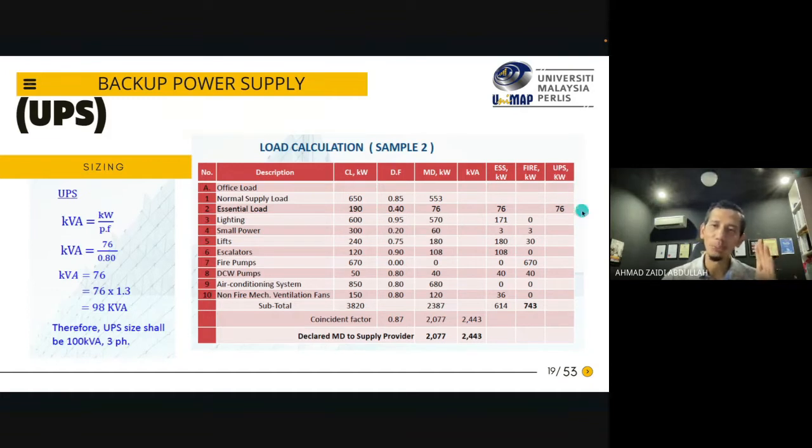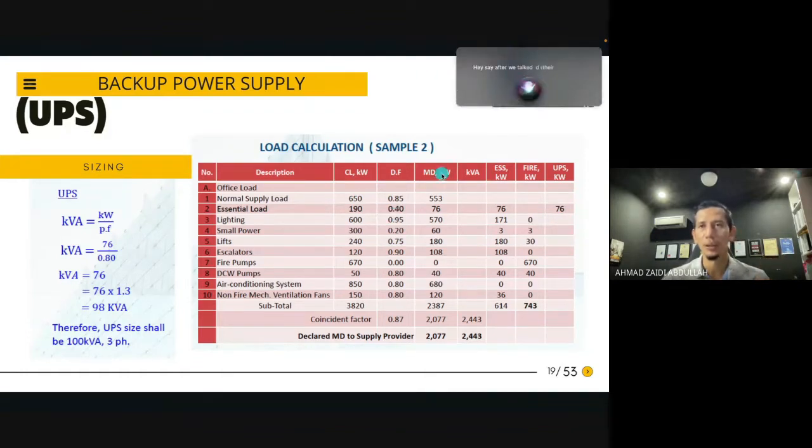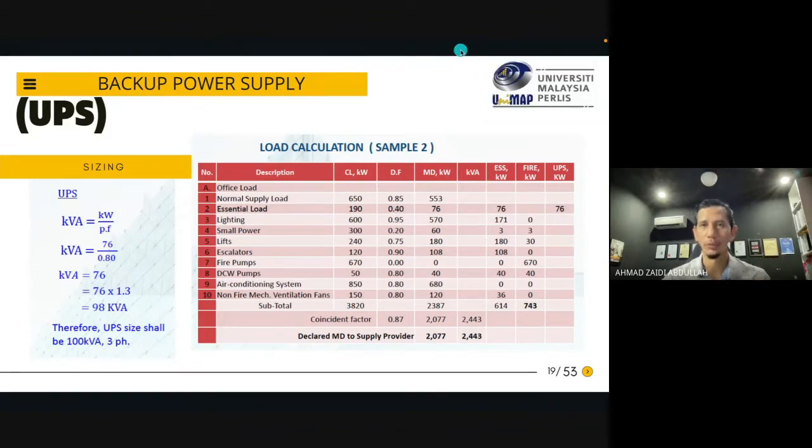Okay, this is UPS. Let's say we decide to cater for the essential load. After we total up the essential load, we get 76 kilowatt that we need to back up from the UPS.